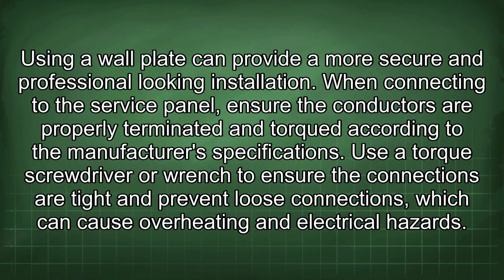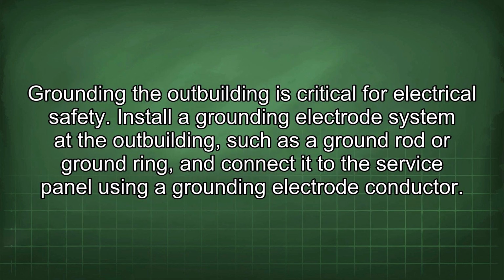When connecting to the service panel, ensure the conductors are properly terminated and torqued according to the manufacturer's specifications. Use a torque screwdriver or wrench to ensure the connections are tight and prevent loose connections, which can cause overheating and electrical hazards. Grounding the outbuilding is critical for electrical safety.